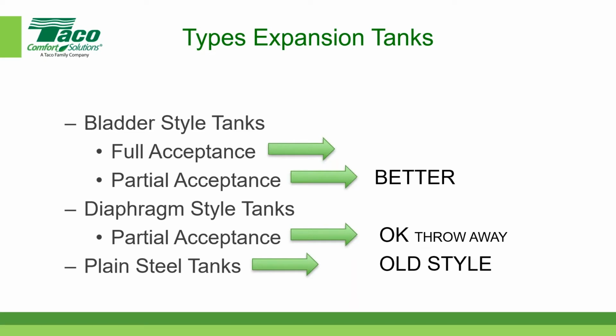Then partial acceptance bladder style tanks - they're better, right? They allow you a little more flexibility. When I say partial acceptance, you'll see what I mean: there's a tank with a volume, and the bladder inside doesn't fill up the whole volume when the water comes in. So there are some sizing issues - maybe a little bigger, up to 100 or 200 gallon type systems, you might want to use a partial acceptance. The bladder in a partial acceptance tank is replaceable in the field.